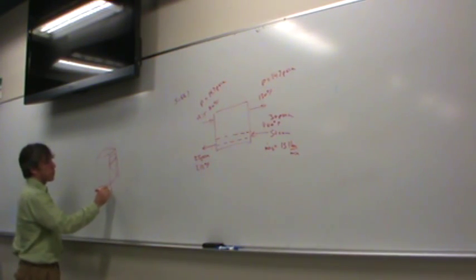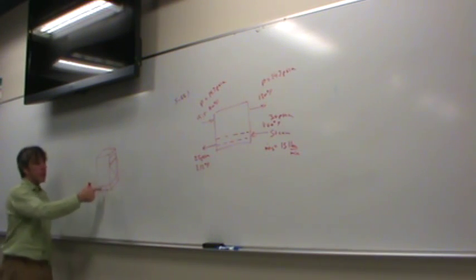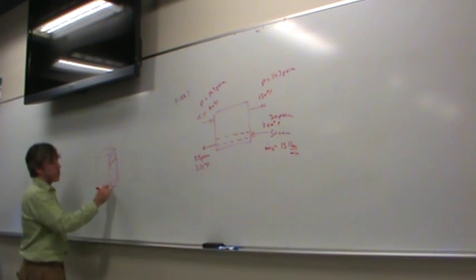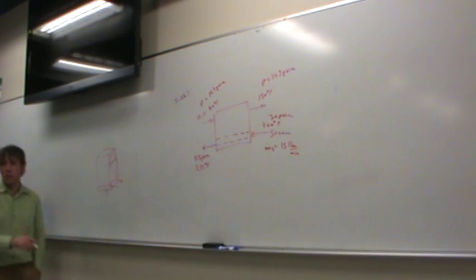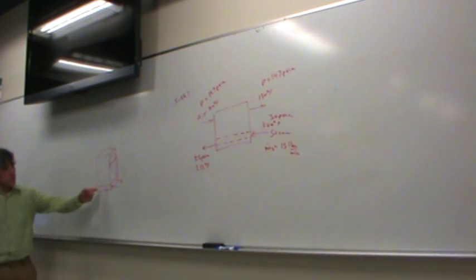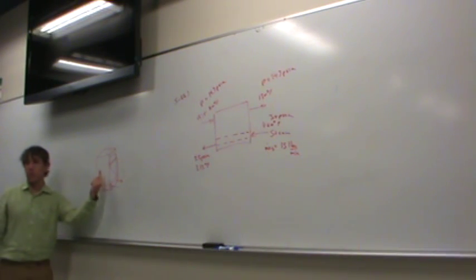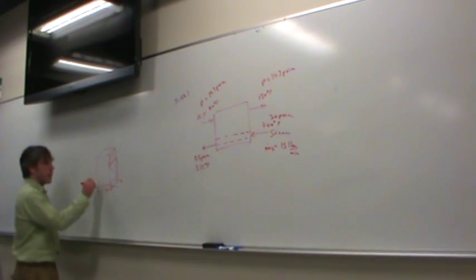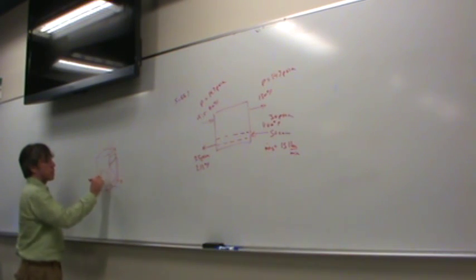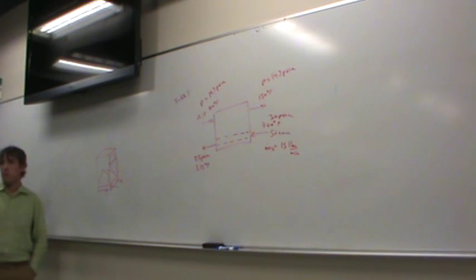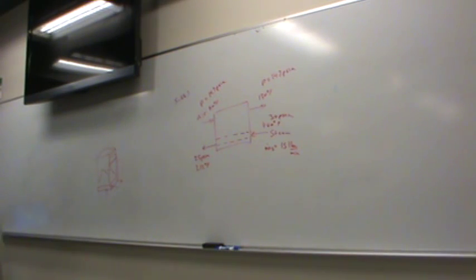So I put a cross-flow heat exchanger where my boiler sends in the hot water. So basically hot water comes in one side and moves out the other. It's just pipes. Now, when I selected this heat exchanger, I knew that air would have to flow through it. Now, there's already an A coil inside of this unit. And that A coil has refrigerant that runs through it. That refrigerant either operates in heating mode during the cold weather, for the heat pump, or in cooling mode as an air conditioner during the summer.